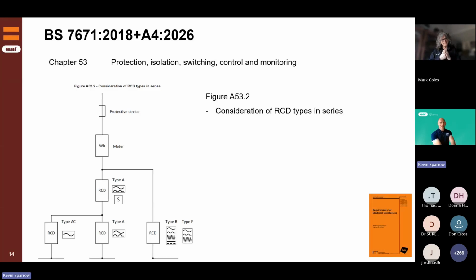Sorry to interrupt. Yes, so you saturate the core with direct current. Sorry, please carry on. No, that's it. There was a thumb wheel that you turned, and what it did, it put DC into the toroid of the RCD, and it locked it, so it would ignore the test that was being carried out and stay closed and in circuit. And that's what happens with these AC type RCDs, that can be blinded by the DC that's being produced by modern equipment like variable speed drives, inverters, that kind of thing.